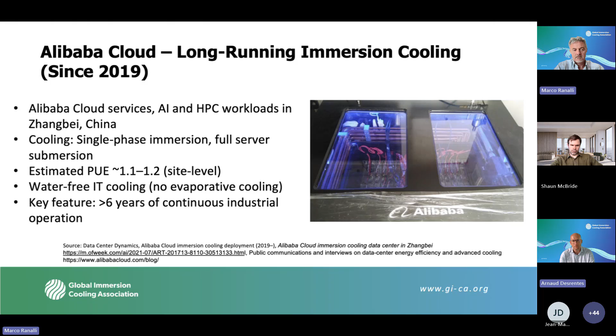Here are just two other examples that we show, but there are plenty of them. Alibaba Cloud: immersion cooling is also used by majors, and this has been a main topic here for many years. In that case, for Alibaba, this was single-phase immersion cooling, full server submersion, to prove that the annual PUE at the site level is below 1.2, and if you look at only the IT part, it's nearer to 1.05. So this is proven to be reliable, and they have fewer issues than when it's cooled with DLC or air cooling.